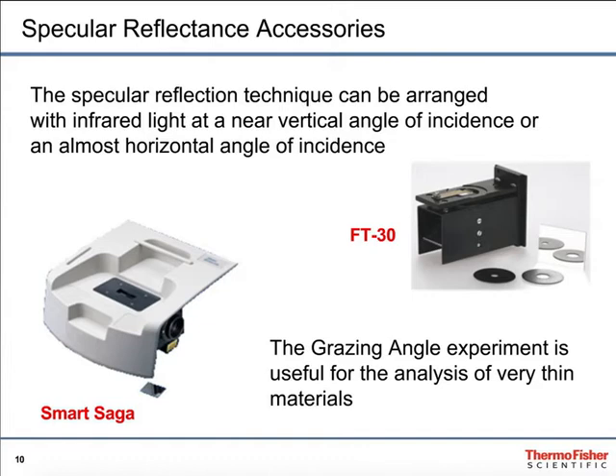Accessories used to do specular reflectance consist of a small number of mirrors that direct the beam onto the surface, then collect the reflected light and direct it through to the optics. Some, such as the Smart SAGA shown here, also involve the use of a polarizer. The beam can approach at a very grazing angle — very steep along the sample — or it could be at a more perpendicular angle. Which you'd want to use really depends upon the thickness of the films you're going to be looking at.